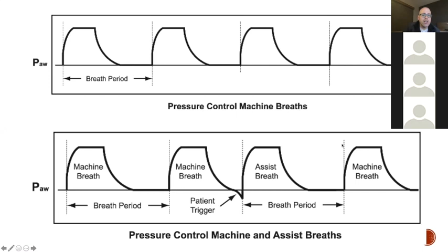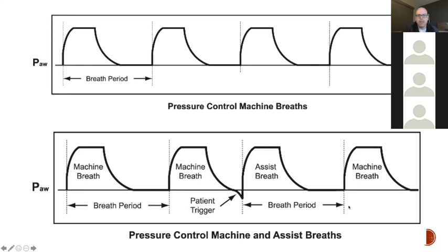The next one on here is assist control. If we look at this, they have a breath, then it's time for the next breath. So they take that breath, and then you'll see this dip below the line. That's the patient making a respiratory effort, taking a little inhalation. When they tried to take that inhalation, they're given a breath. The machine sensed that and gave them a full breath, because in assist control, they get that fully assisted breath. You can see that it fell into the next breath period, so it counts as one of their breaths for that minute. Then they hit their next breath cycle, so they got another machine breath given to them, even though they didn't try and inhale for that one. So that's assist control. This next graph that we're going to look at is SIMV.